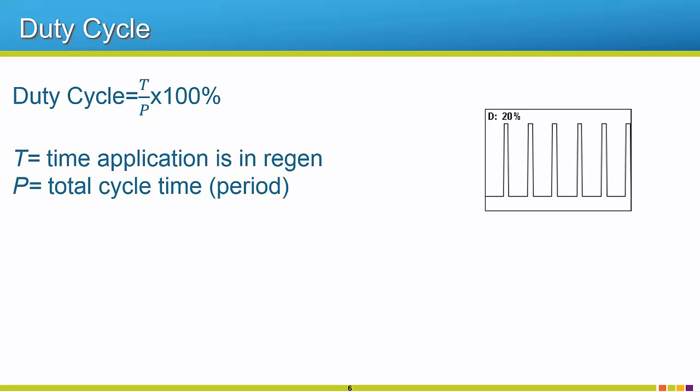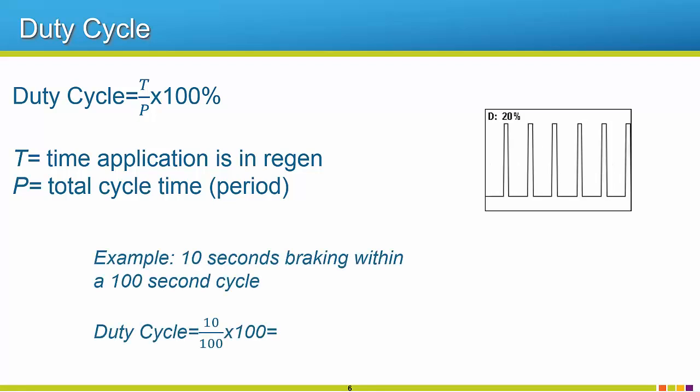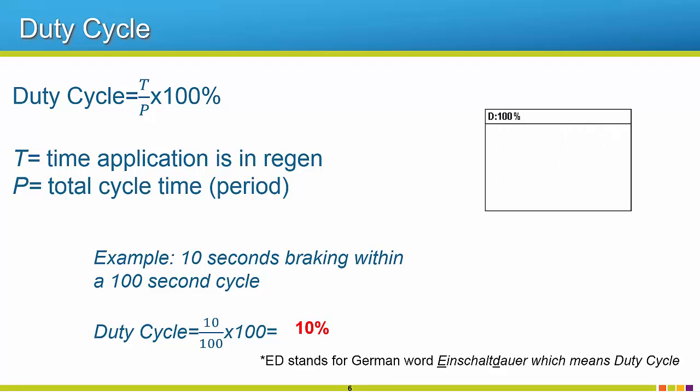Before reviewing the available options for controlling regenerative energy, it is important to understand the term duty cycle. Duty cycle is expressed as a percentage. So when we are talking about regen, this percentage reflects how much time out of one cycle an application is in regen. Knowing this, our example with the downhill conveyor may have 100% regen if the conveyor is fully loaded. This is considered continuous regen. The less time an application is in regen, the lower the duty cycle. This is key information to know when you are matching a regenerative option to a given application. One thing to note is that Yaskawa often lists ED instead of duty cycle when it comes to ratings of regenerative components. ED simply stands for Einschaltdauer, which is actually German for duty cycle.